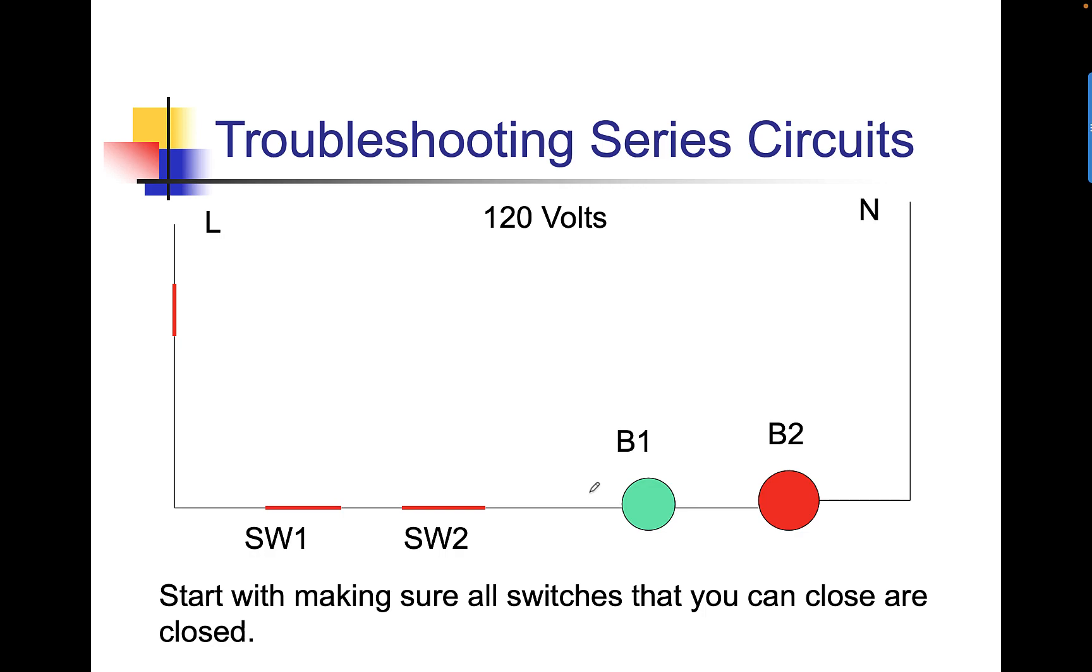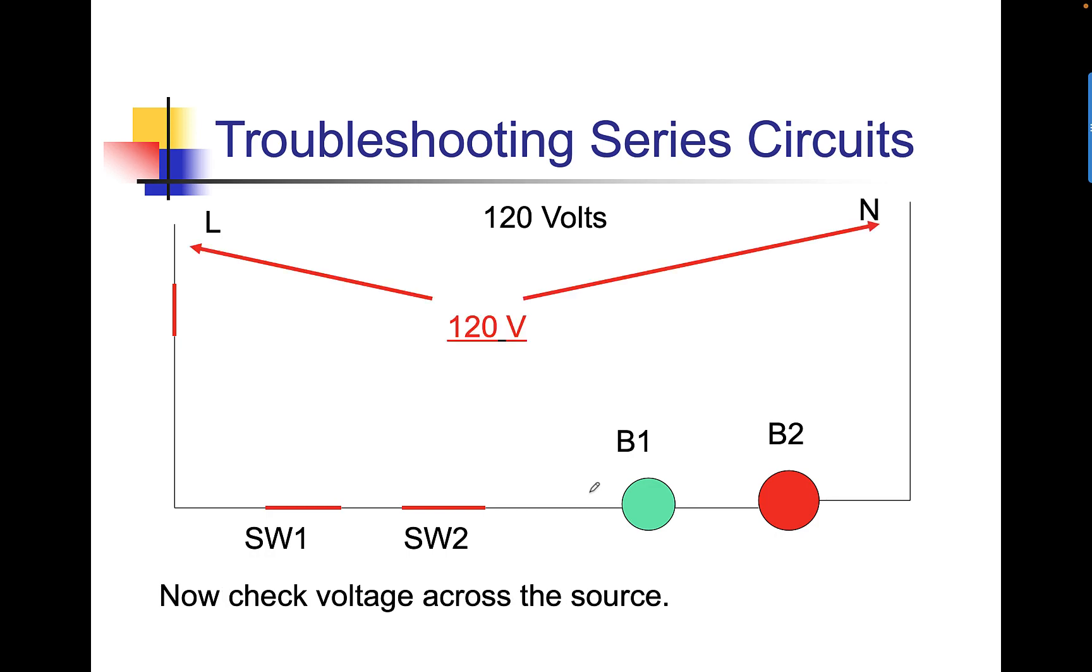So when you're troubleshooting a series circuit, start by making sure all the switches that you can close are closed. And the reason I say that you can close is because a lot of times switches are part of devices and you might not be able to see if they're open or closed just by looking at them. You've got to use your meter. Now check voltage across the source. That's the number one spot. Check voltage across the source. Then go across every switch. Note that I'm leaving one meter lead right on line because from our last lesson on meters, we know that voltage across a closed switch is zero. Voltage across an open switch is source. So we're going to go across and we're going to just continue hopscotching through the circuit.